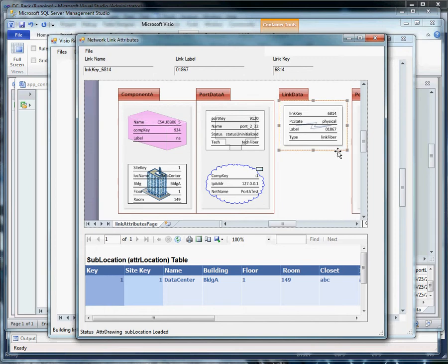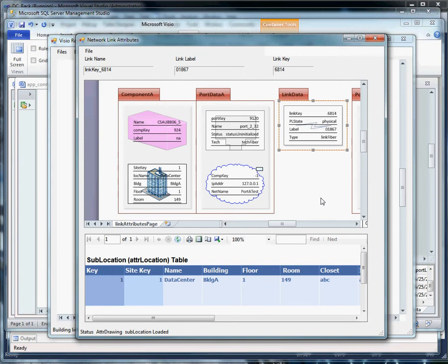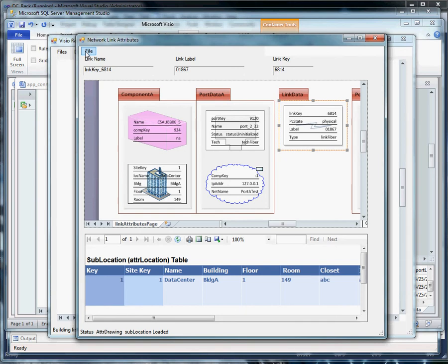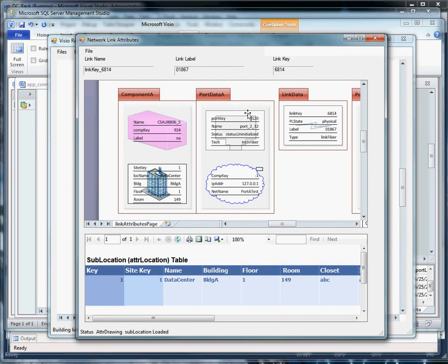An extension for the link data might be an additional table in the database that has VLAN information. And then we could put list items underneath this to show what VLANs are associated with this link data. But it gives us a pretty powerful tool for working with how do we want to drill down. Would I want to create diagrams for each of the cables in my network? Hardly. In a medium-sized data center it's not unusual to see tens of thousands of cables. But it does give us the ability to pull up an individual cable and pull up the detail information on it.